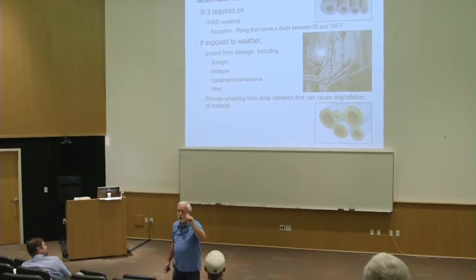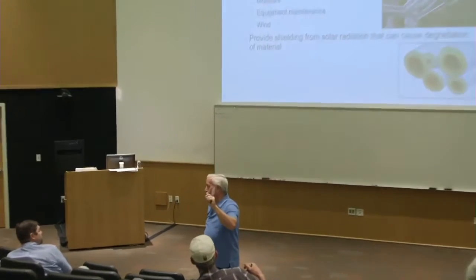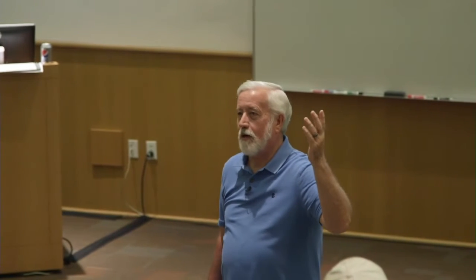The mechanical code has said you have to have R4 insulation on your air conditioning line sets. The energy code says R3 by definition of the temperatures and stuff within the gas. Most line sets come with R3 on them. Don't make someone tear it off or add insulation to it. The main purpose of that insulation on the line set, the refrigerant lines, is condensation prevention. That's refrigerant coming back to the outdoor unit. It's already done its cooling. The only thing it's trying to do is provide some cooling to the condensing unit, the compressor itself.